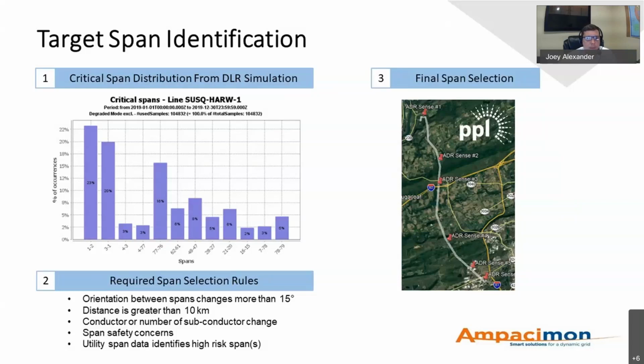By the fact that we model out every single span of this transmission line, we're able to put on a distribution curve the percentages of the time that each span was the limiting or critical span in that line.